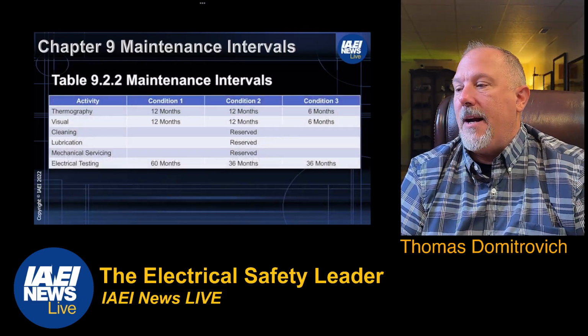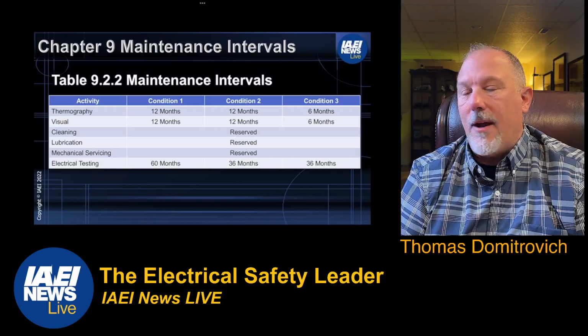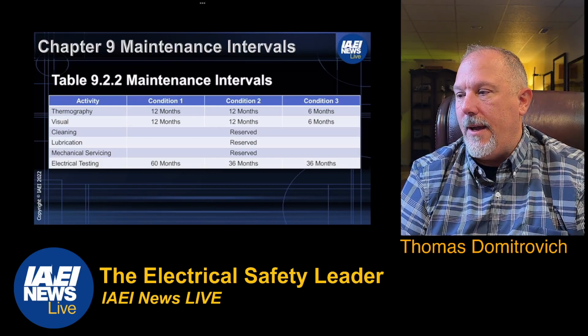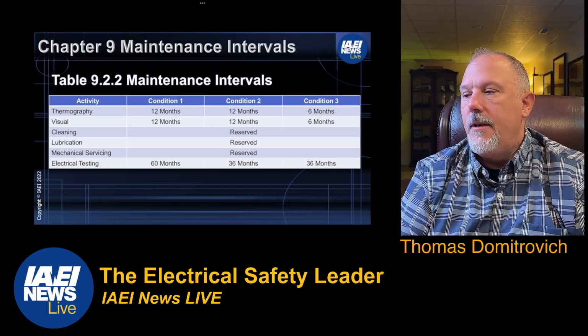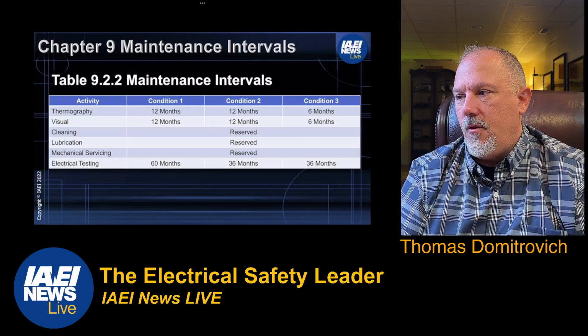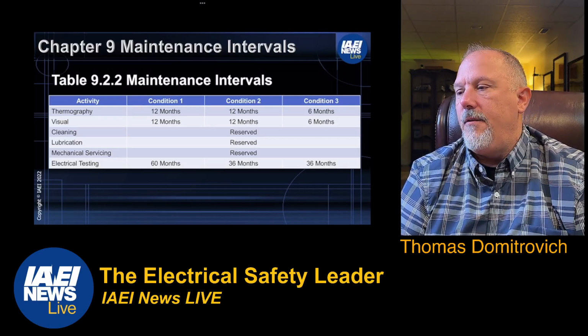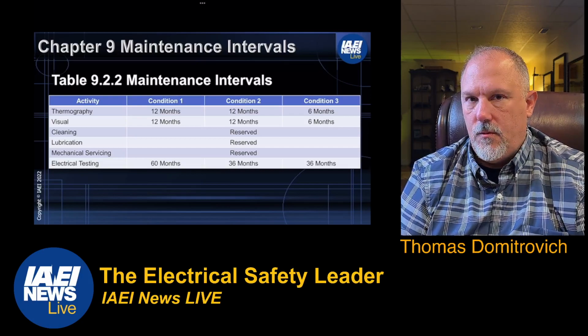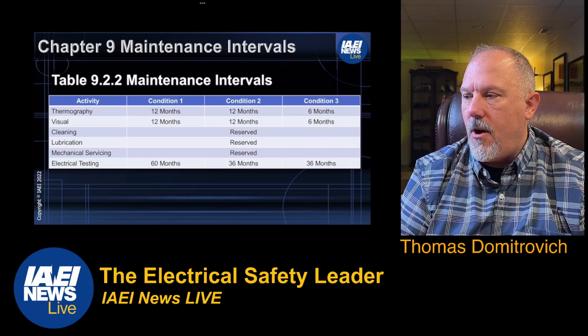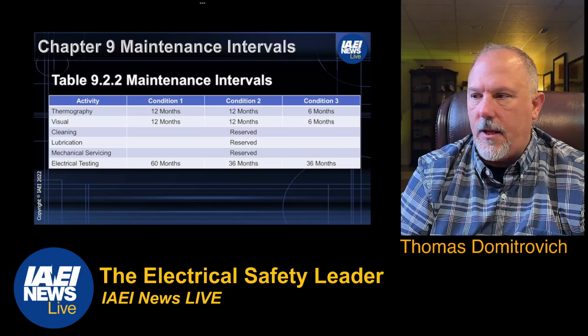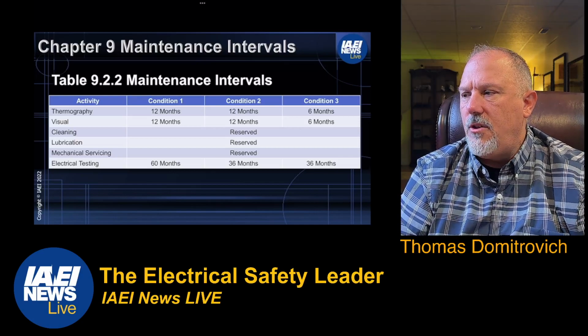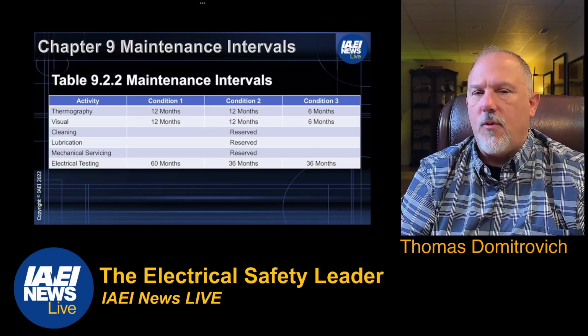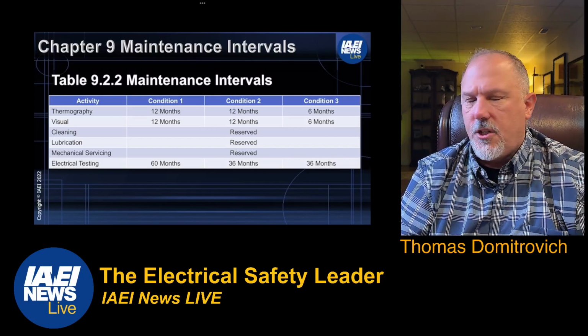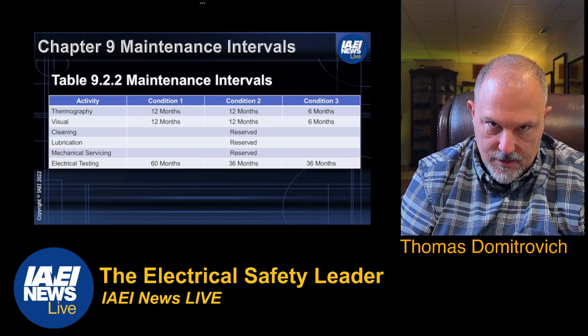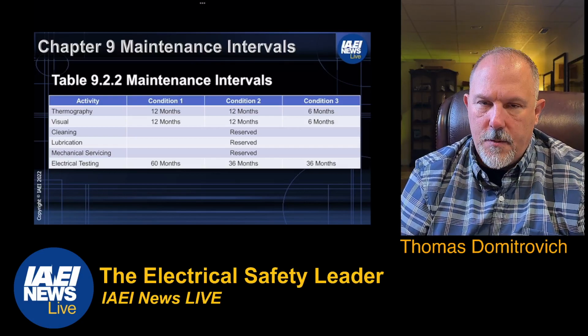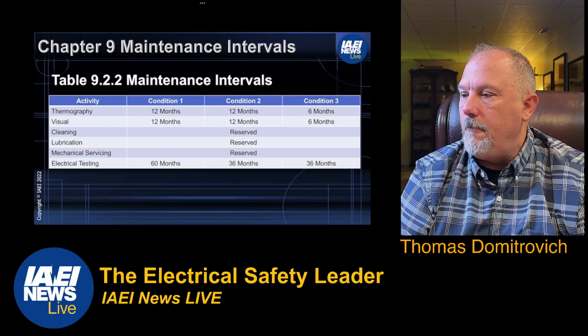If I think about grounding and bonding and go through table 9.2.2, there's a row in there. Thermography applies generally above it, telling us we should do thermography every 12 months for condition 1, 12 months for condition 2, and 6 months for condition 3. I'll try to help you understand conditions 1, 2, and 3 as well.